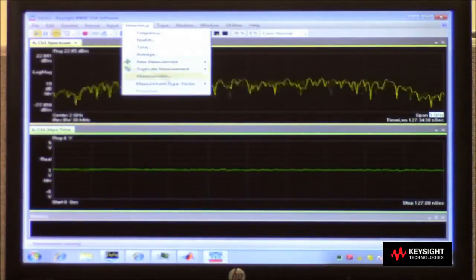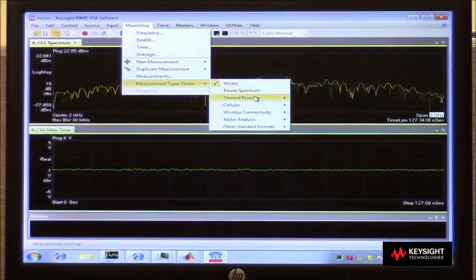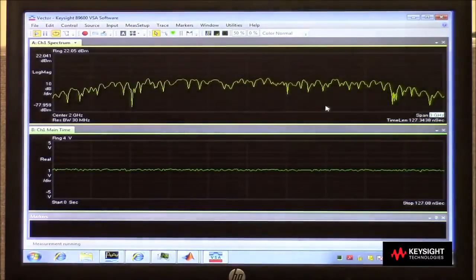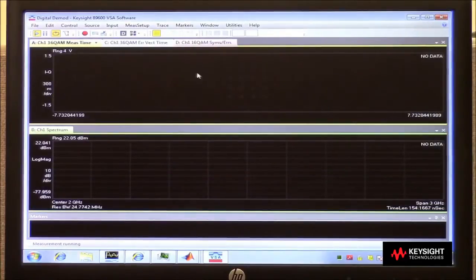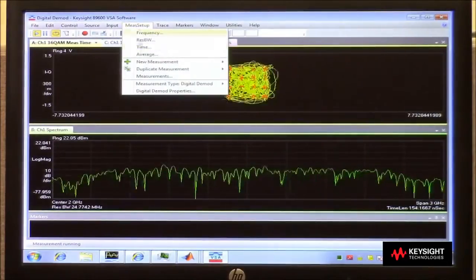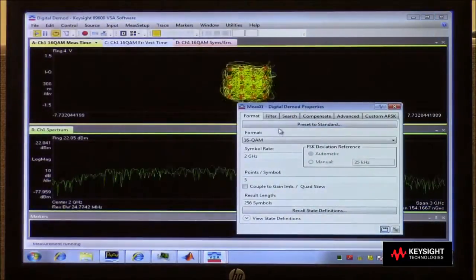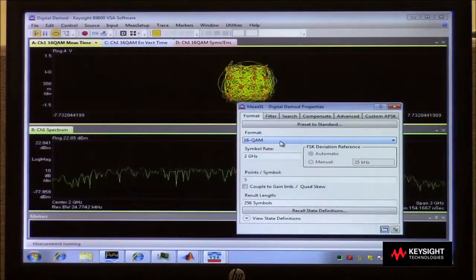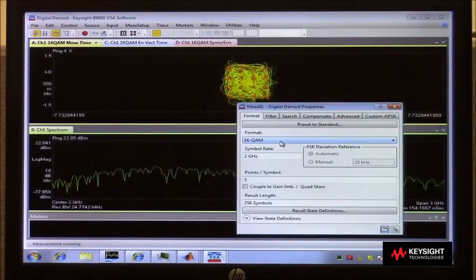Then in the measurement setup menu, I can go down to measurement type and choose, under general purpose, digital demodulation. And more specifically, under the digital demodulation properties, I have set up 16 QAM. That's the type of signal that I have here.